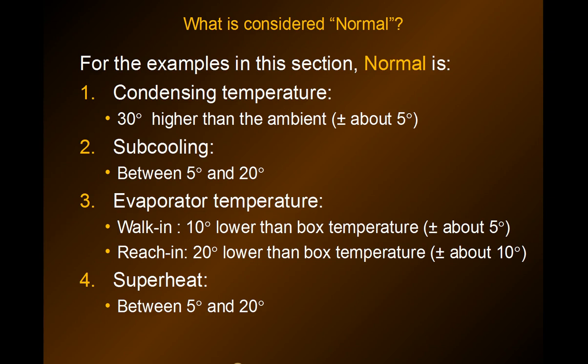For the troubleshooting examples in these videos, normal means the condensing temperature is about 30 degrees higher than the ambient, plus or minus 5 degrees — that's also on the cheat sheet. Normal subcooling is between 5 and 20 degrees. Evaporator temperatures for a walk-in are 10 degrees lower than the box temperature, and for reach-ins, 20 degrees lower than the box temperature, with a pretty wide margin plus or minus. Normal superheat is between 5 and 20 degrees.